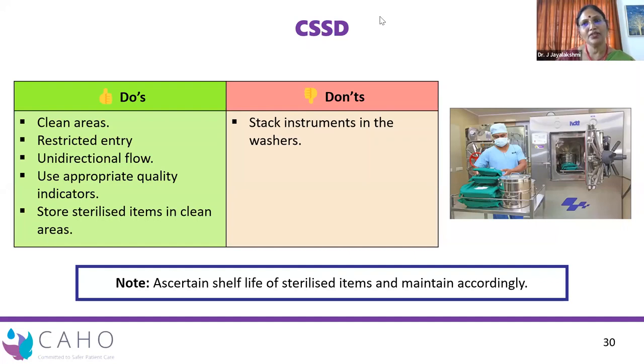Use appropriate methods of sterilization, with instruments calibrated by trained personnel, wearing appropriate protectives, and knowing the safety precautions for each one. Also use quality indicators to validate the sterilization process, because you can't visually tell if an instrument is sterilized after going through the process. So you need something that changes color, confirming the time, temperature, and pressure parameters were met.